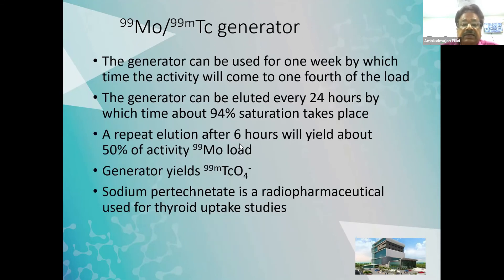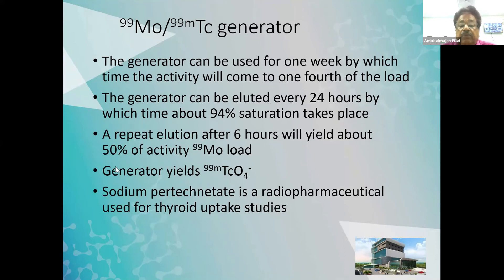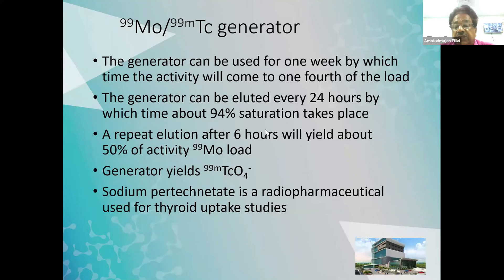The pertechnetate is a radiopharmaceutical. The generator can be used for one week, by which time the activity comes to one-fourth of the load. It can be eluted every 24 hours, by which time about 94% saturation takes place. If you want a repeat elution — say you got 500 millicuries in the morning and need more activity in the evening — after six hours of growth you will get about 50% of the molybdenum load, for example around 250 millicuries, allowing you to schedule a few more studies.